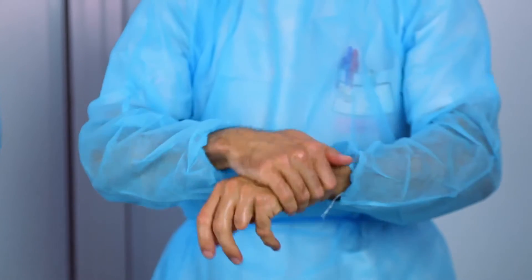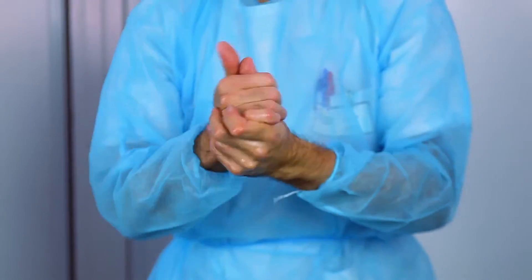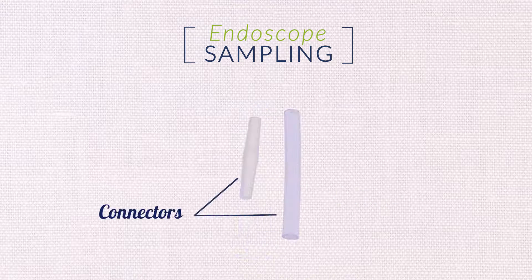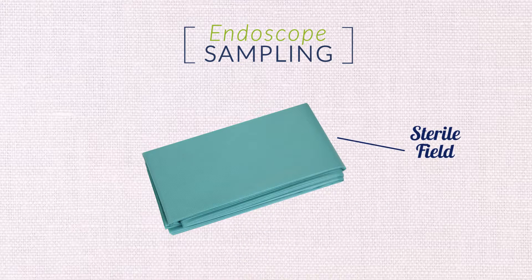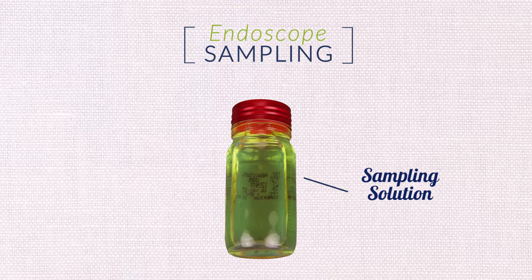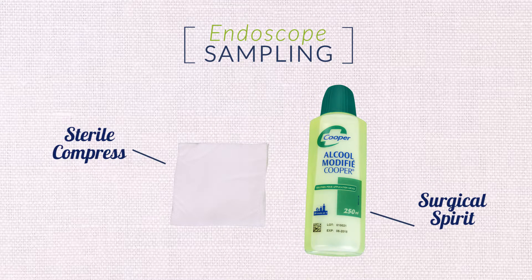For the endoscope sampling, the following materials are needed: one endoscope (in this case a gastroscope), syringes, connectors, one sterile field, one sampling bottle, one sampling solution, one sterile compress with surgical spirit, and one sampling sheet.